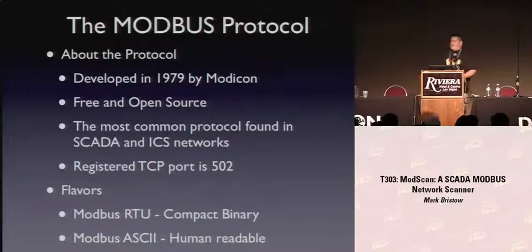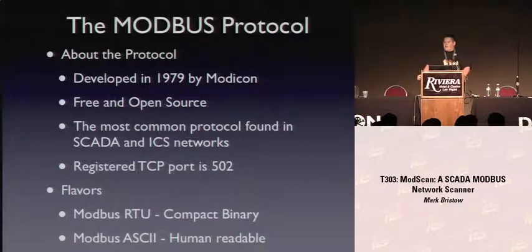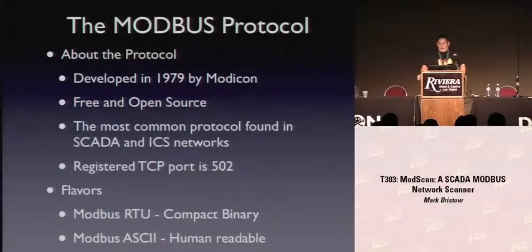Depending on who you ask, it's the most common protocol out there - I'd say that's probably a bit of an overstatement, but almost every major control system network I've seen has at least some element of ModBus running on it, because it's so old and well-established. ModBus TCP is registered on port 502. It comes in two flavors: RTU, which is binary, and ModBus ASCII. They're basically the same thing except for the compression format and they use different CRC versus LRC checks.